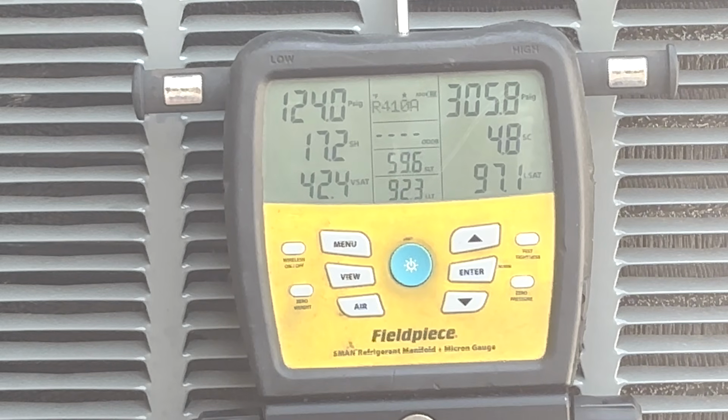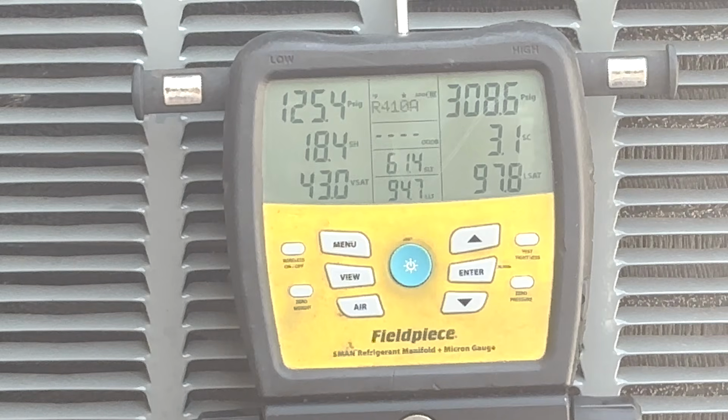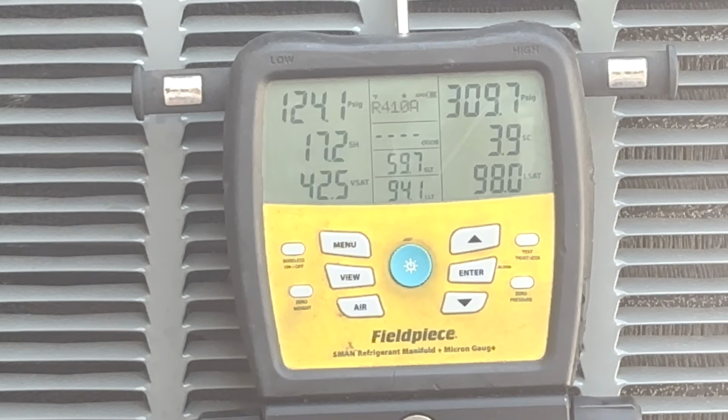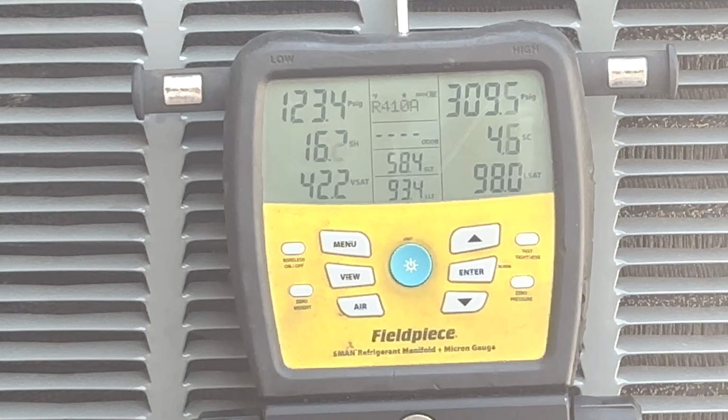So the steps that we would need to fix this unit would be to recover all the refrigerant. Once all the refrigerant is recovered, we would need to remove the dryer. After the dryer is removed, we'll need to install a new dryer and then pull a proper evacuation down to 500 microns. You want to make sure that you're not pulling your vacuum too fast or using a high CFM vacuum pump and freezing any moisture. We want to make sure that we're pulling a good, slow, steady vacuum, get down to the proper microns, and then we want to weigh in a factory virgin refrigerant charge that we know came out of a bottle that has never been tampered with.